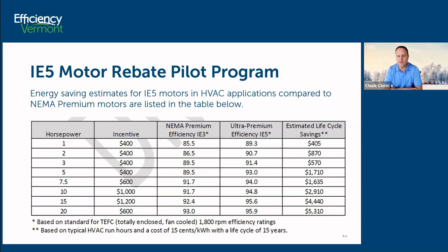In columns 3 and 4, you'll see the delta in nominal efficiency. This is the nameplate efficiency on the motor, and it is the full load rated efficiency. The savings on the right side are in dollars. The kilowatt hours behind that are predicated on the delta between efficiency in columns 3 and 4, and a motor running at 1,800 RPM and 15 cents a kilowatt hour for a 15-year motor life, which is a pretty typical lifespan and prevailing cost of electricity for HVAC customers. Excuse me.